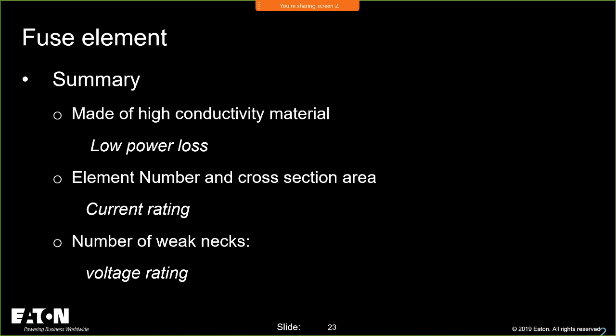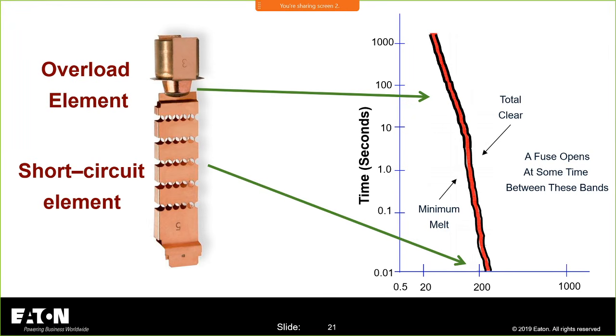And then the number of weak necks gives you the voltage rating, which I think is an interesting thing. So if you look at this, all these little pinch points help you establish the voltage rating. And that's why, if you ever looked at a medium voltage fuse, the element inside is not straight like this, because I can do this since it's only applied at 600 volt. But when I'm making a 15 kV fuse, etc., I need a lot more of these pinch points. I need 1, 2, 3, 4. If I actually made a fuse long enough to put it straight like this, it'd probably be a few feet long. So what we do in a medium voltage fuse is we coil that inside of the fuse.